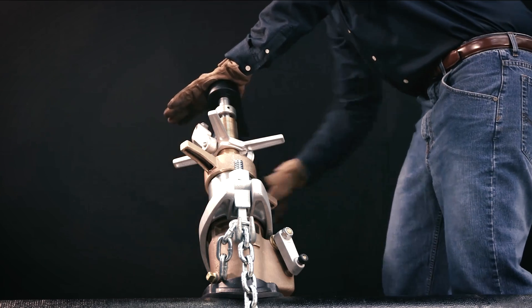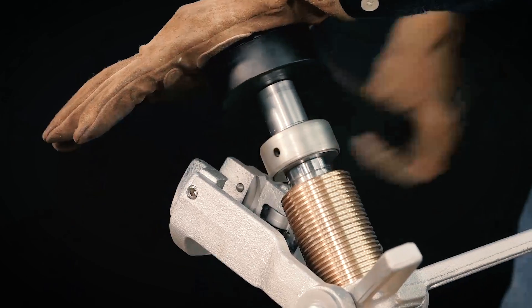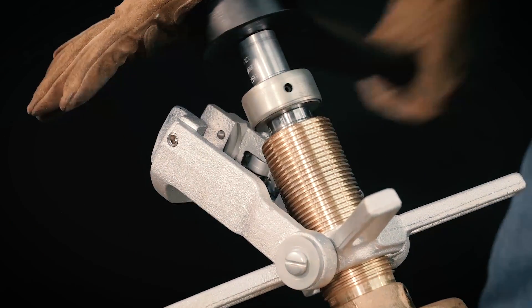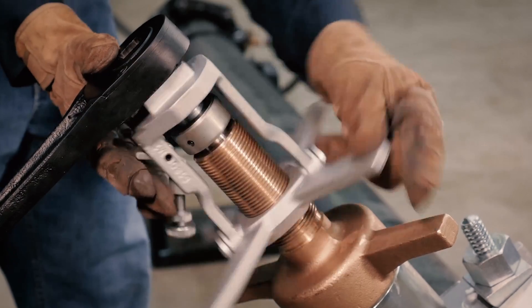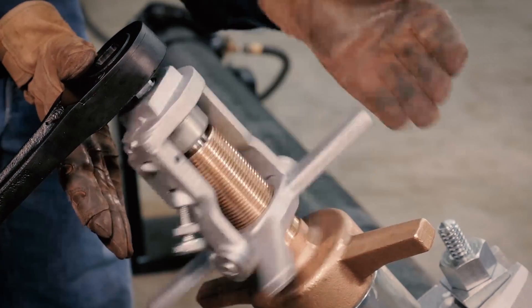At this point the feed yoke is no longer needed and is removed. Continue the tapping operation until the tapping line of the boring bar is flush with the top of the feed sleeve part of the cap.